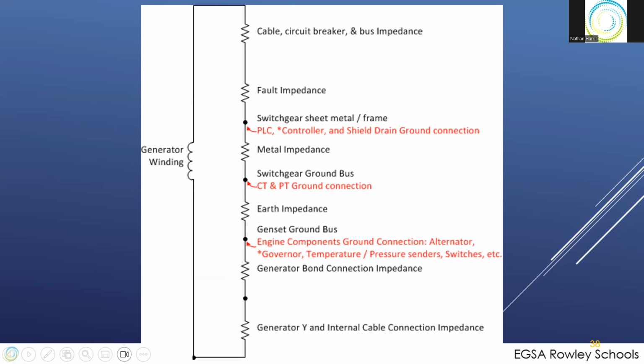So if we have one generator winding that's generating 277 volts, let's say, and there's a common ground point. The ground got cut off there at the bottom, I apologize. But out of this generator winding, there's cable and circuit breaker and bus impedances. So the cable from the generator to the switchgear bus, to the breaker contacts onto the switchgear bus itself, and then the bus is where the fault was in this scenario. There's a fault impedance. That's the arcing, burning impedance of a fault.